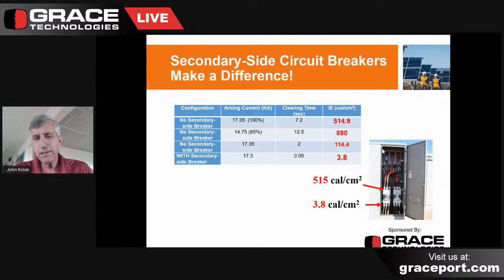But if we use the secondary breaker and it cleared, you'll see that it clears in only 3.8 calories. So looking at that little graphic there, if you took your voltage readings on the high side or the source side, if you will, of that circuit breaker, there'd be 500 calories. On the very low side of that same exact breaker, there would only be 4 calories basically in the system. So this is important to consider from a safety standpoint for training, but it's also important from the engineering standpoint. If we can do anything to lower that incident energy, we can get it from where it would be certain death at 500 calories down to 4 calories, which would be survivable wearing street clothes, essentially.